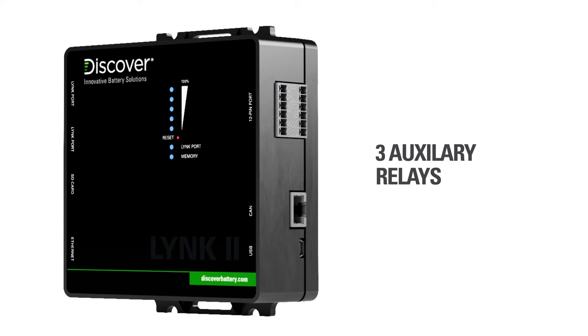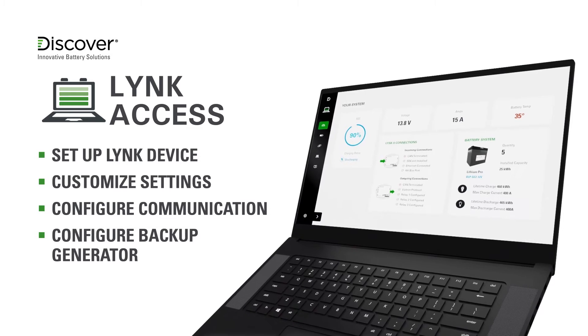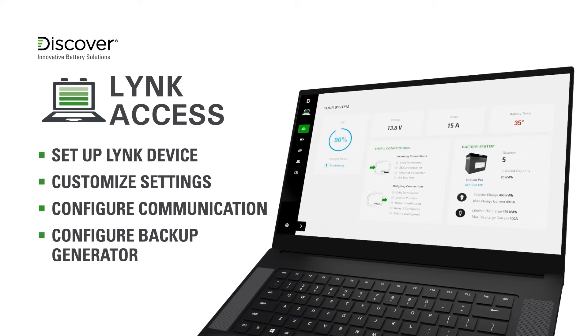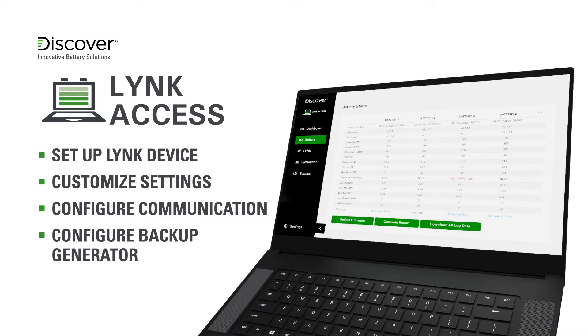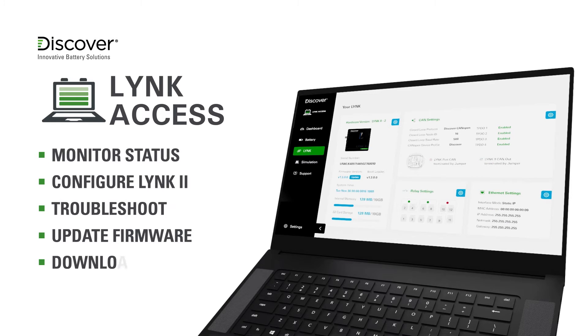LYNK ACCESS software makes configuring communication between an off-grid inverter system and LYNK II simple. With LYNK ACCESS, it's also easy to set up the start and stop parameters for a backup generator. LYNK ACCESS also enables installers to update battery module firmware and troubleshoot systems by downloading battery module data.